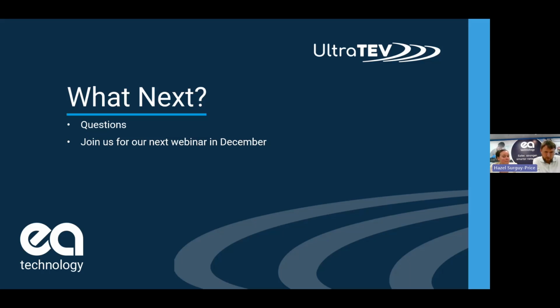Okay, so hopefully through the webinar you've seen we can test HV cables. You do that through use of an HFCT normally. That will go around the earth strap of the cable and allows you to do PD detection and TDR for location down the cable. You can also do them offline.